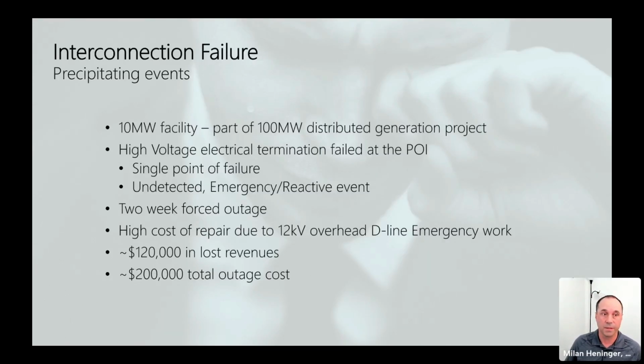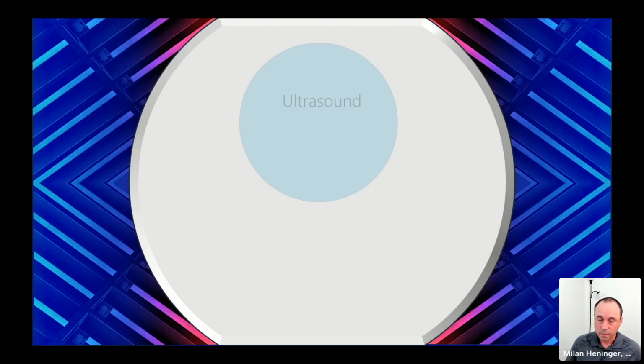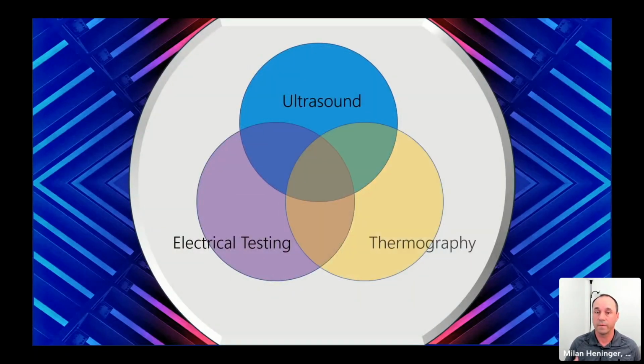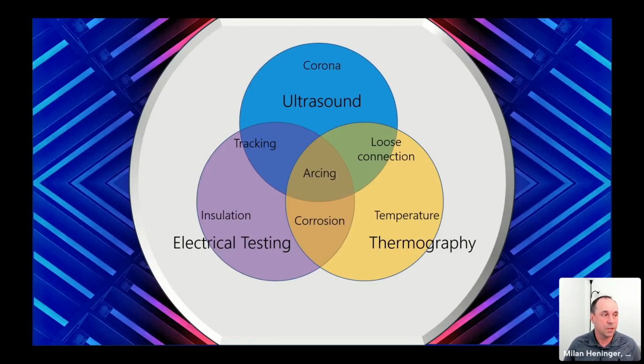So there's a few options. We have ultrasound, we have electrical testing, and we have thermography as our main toolkit for this type of issue, right? Where we've just had a bad connection that failed. Because the system is online, we really didn't have a lot of options in terms of online electrical testing for this particular design. We also weren't too worried about insulation being an issue. We were really more worried about the tracking, loose connections, and some high temperature connections as well, due to, frankly, some corrosion that was on the fittings that when it was assembled, it wasn't properly cleaned off.